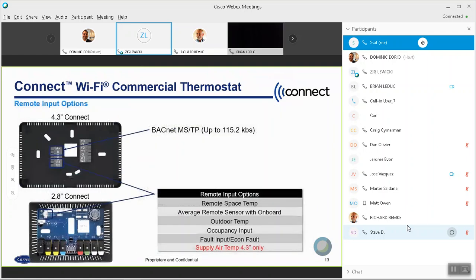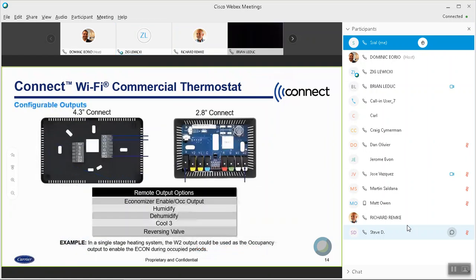Again, both of these have one remote input, so you could use that remote input for things like remote space temperature. You could average it, or use it as a remote outdoor temperature or occupancy input. You can use it for voltage detection on the economizer for the Title 24 and IECC 2015 compliance. And in the case of the 4.3 version only, that can also be your supply temperature input.